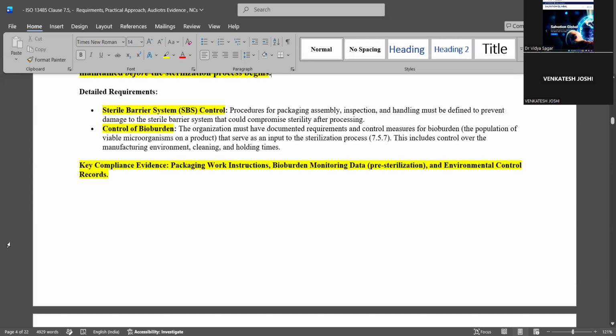And control of bioburden. This I already discussed. You should always control bioburden in your room by cleaning your machines, cleaning your rooms with antiseptic agents, or cleaning the devices. As I told, though you are sterilizing them, you still need to clean so that the bioburden will come down. You clean with spirit or even simple water, or you flush it with some water so that the microorganisms will come out, or you flush it with air. If it is inside the lumen in plastic, you can flush it with air. The particles and bioburden will become less. It's not that it becomes zero, but it will become less.